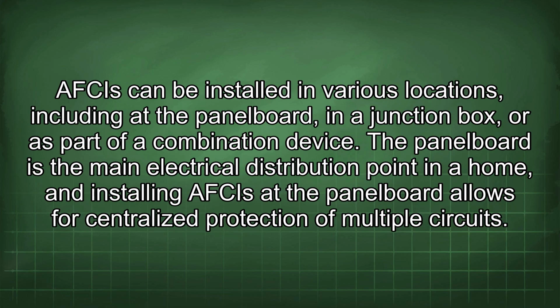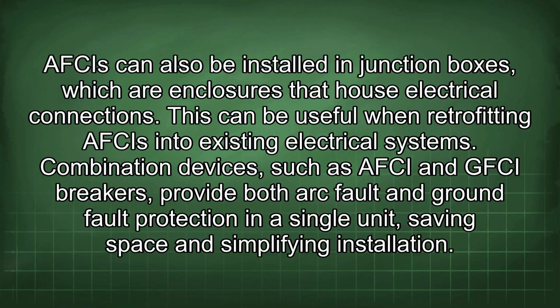AFCIs can be installed in various locations, including at the panel board, in a junction box, or as part of a combination device. The panel board is the main electrical distribution point in a home, and installing AFCIs at the panel board allows for centralized protection of multiple circuits. AFCIs can also be installed in junction boxes, which are enclosures that house electrical connections. This can be useful when retrofitting AFCIs into existing electrical systems. Combination devices, such as AFCI and GFCI breakers, provide both arc fault and ground fault protection in a single unit, saving space and simplifying installation.